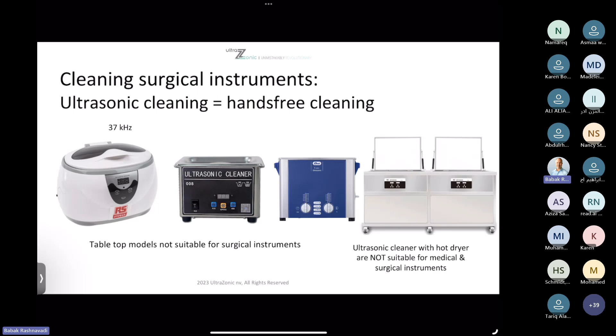Now, I can tell you, if I should propose that in a hospital in Europe or in any hospital where there are more regulations and IFUs that they have to follow, it is actually not allowed anymore, not at all, that you use an ultrasonic cleaner and right away after ultrasonic cleaning, you put it in the hot dryer and then consider it safe to reuse it again. So you cannot do that. So please stop investing in that kind of material or machine, because it's not helping at all, okay? So you're really facing other problems. Next, please.